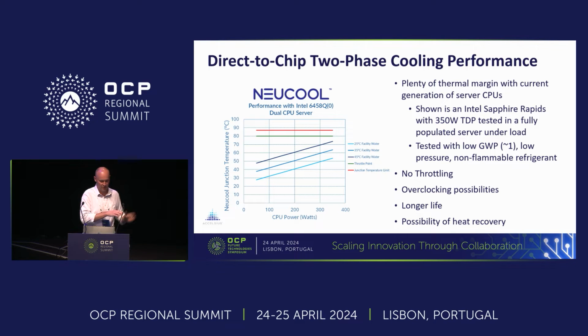This plot shows junction temperature versus CPU power. The top two lines: the topmost is the max temperature before the Intel chip would shut off, and the green line is the throttle temperature, about 80 degrees Celsius. Even with 45 degree C facility water coming into a fully loaded rack, the max temperature we saw at full power on these CPUs was roughly 73 degrees C, well below the throttle point.